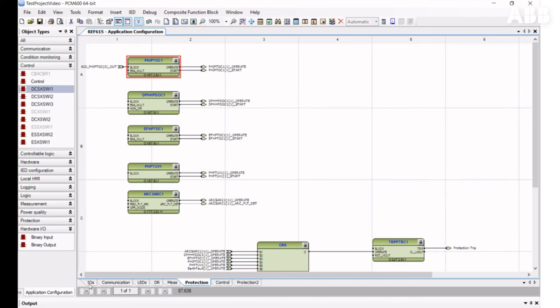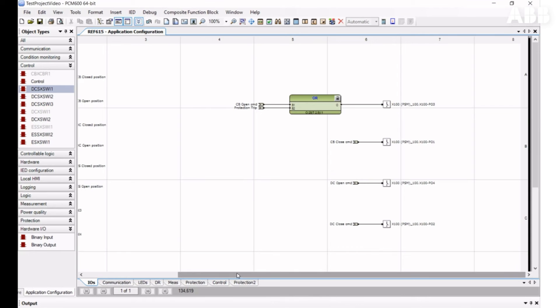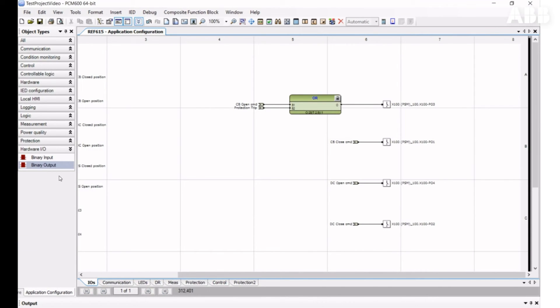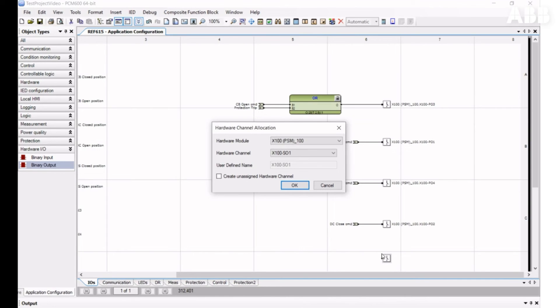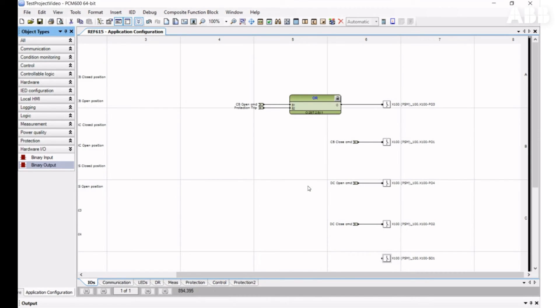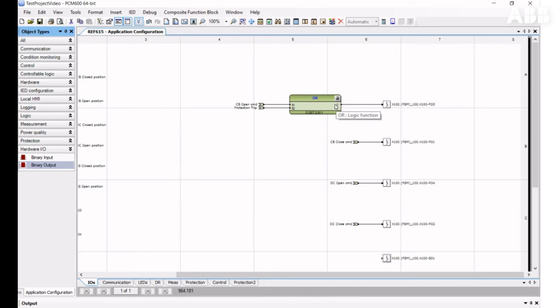To insert a binary output, choose Binary Output from the Hardware Inputs/Outputs section in Object Types and drag and drop it to the configuration. Then select the Hardware Module and Hardware Channel and click OK. Every binary output can be used only once in the configuration. If you need to connect several signals to the same binary output, use the OR function block to connect variables through it. There are three types of binary output: high-speed outputs (HSO), power outputs (PO), and signal outputs (SO).